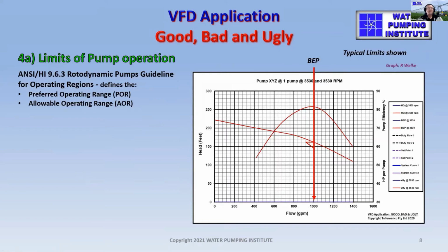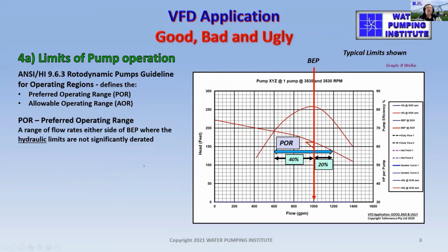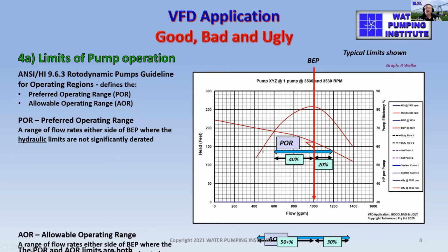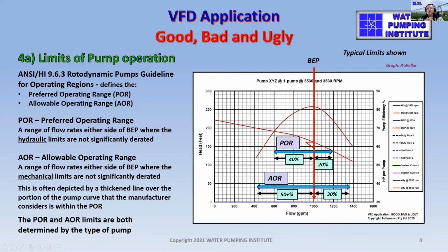According to your HI 9.6.3 Rotodynamic Pumps Guide, we have some operating regions. We have the preferred operating region of a pump, and it's something like 20% to the right-hand side of best efficiency point and 40% to the left. That's what we should be really striving for. If we can't do it, sometimes the overlap of pump sizes doesn't allow us to get that close. We can go inside the allowable operating range, which extends 30% to the right of best efficiency and 50% to the left of best efficiency. So these limits are both determined by the type of pump, so there are variations.